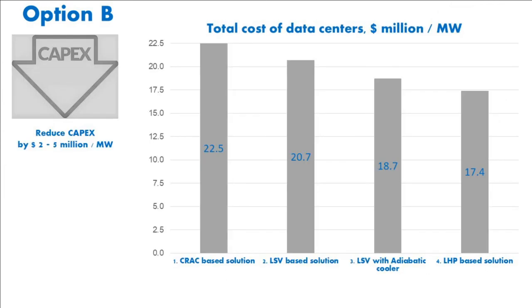We see a not obvious trend. The more efficient the system, the lower its total cost. And the main savings are in the energy sector, secondly in the UPS, and then in third place the cooling system. Therefore, I want to draw attention to the fact that it is important to look at the total cost of construction and not the individual cost of the components.